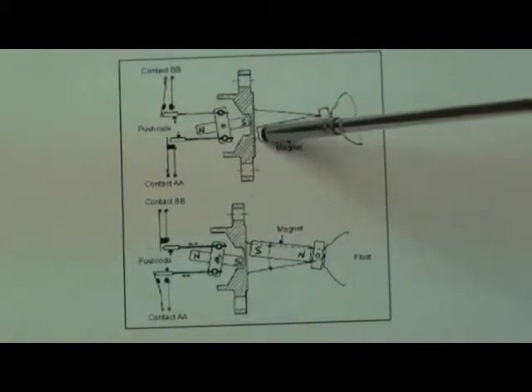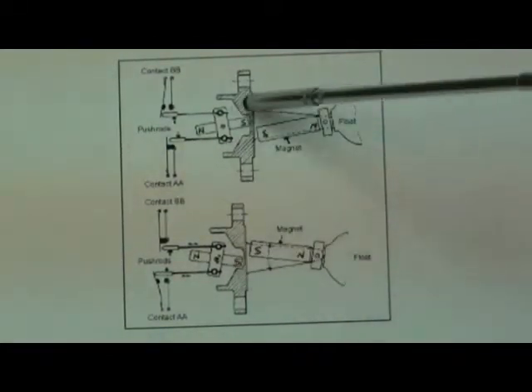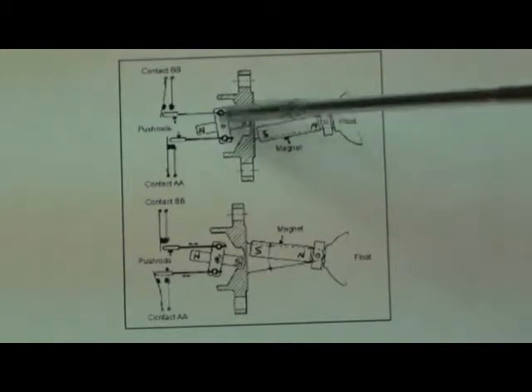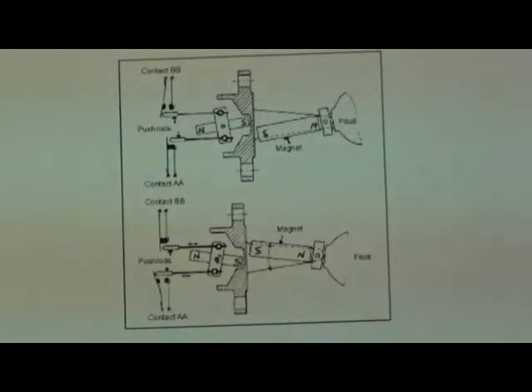So we will have south pole facing a south pole, and consequently the south pole in the switch head mechanism will be repelled and snap over. This causes the snap action operation in the switch mechanism.